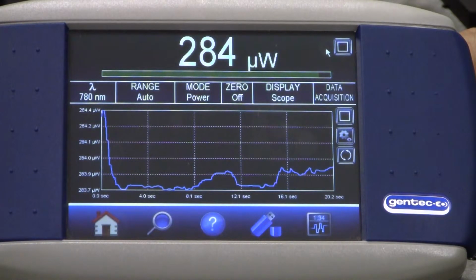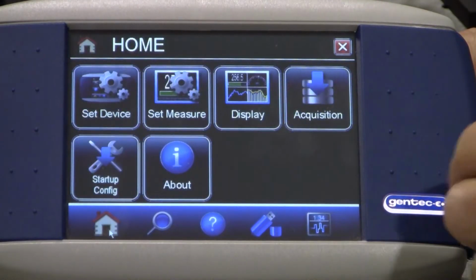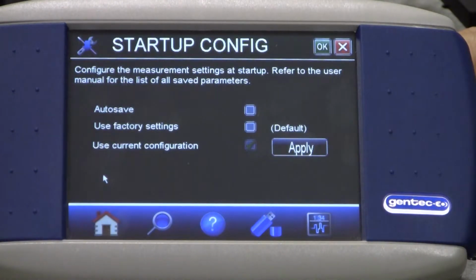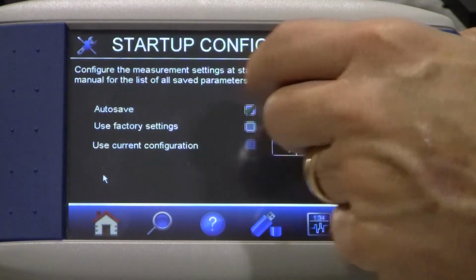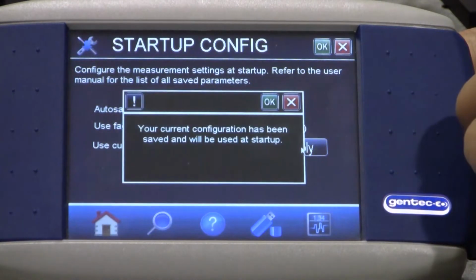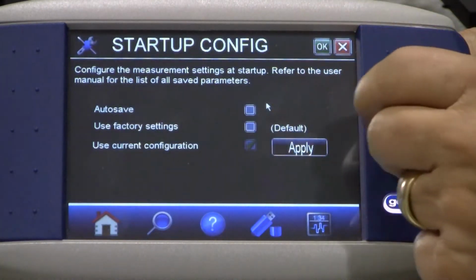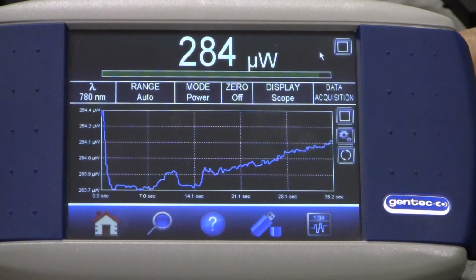If you want Maestro to remember all of your settings for the next time you use it, you need to save those settings as follows. Touch the Home button, then select Startup Config. Now select Auto Save, Apply, and then OK. This will save your current setup, so when you turn the instrument off tonight and power it up tomorrow, it will have saved all your settings like wavelength, range, display, and more.